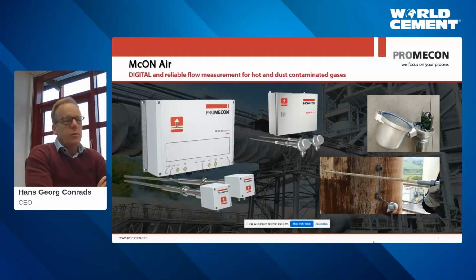So this is really the difference to most of the other gas flow measurements in the world. Process gas measurement is rare. You don't have many systems out there in the industry that can really measure process gas as I have defined it. So gas that can be 100 degrees C, but could also be 1,000 degrees C, even 2,000 degrees C. Gas that can have up to 100 grams of dust per cubic meter, not 100 milligrams.